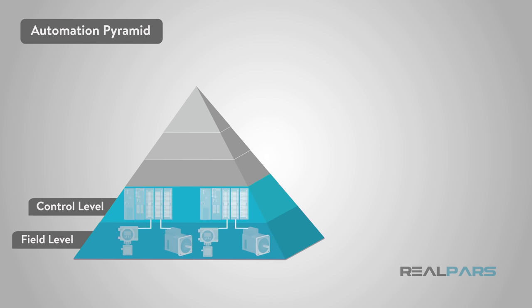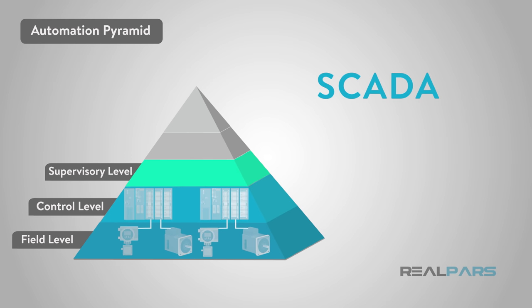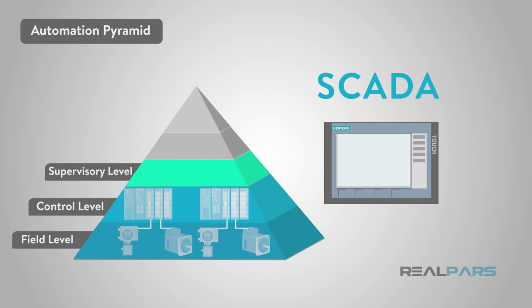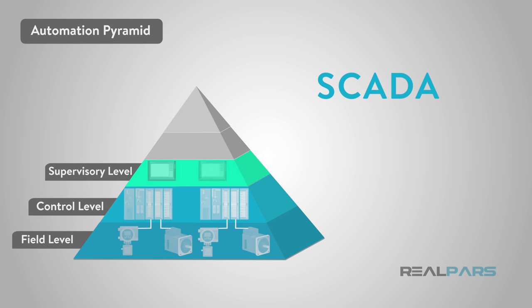The third level of the automation pyramid is known as the supervisory level. Where the previous level utilizes PLCs, this level utilizes SCADA, short for Supervisory Control and Data Acquisition. SCADA is essentially the combination of the previous levels used to access data and control systems from a single location. Plus, it usually adds a graphical user interface, or an HMI, to control functions remotely.